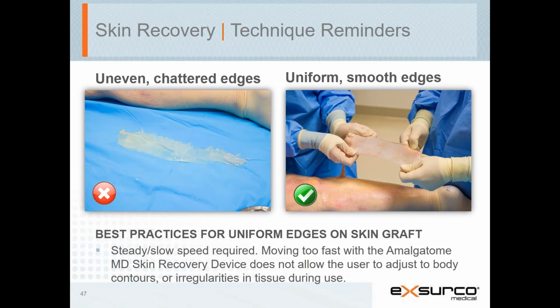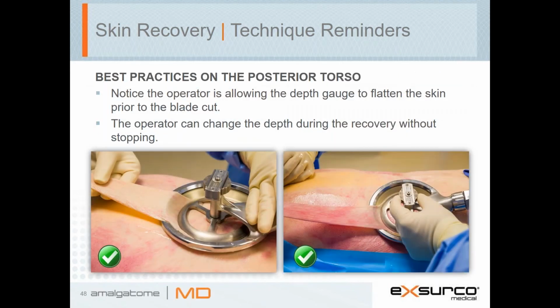Best practices for uniform edges on a skin graft. A slow, steady speed is required. Moving too fast with the Amalgatome MD skin recovery device does not allow the user to adjust to body contours or irregularities in tissue during use. Best practices on the posterior torso. Notice the operator is allowing the depth gauge to flatten the skin prior to the blade cut. The operator can change the depth setting during the recovery without stopping.